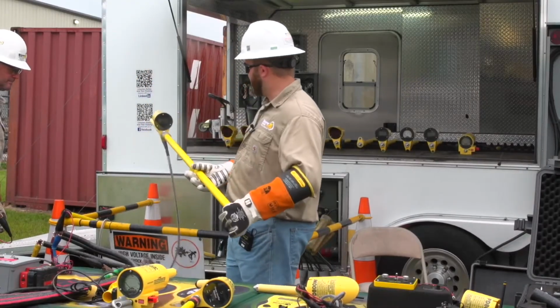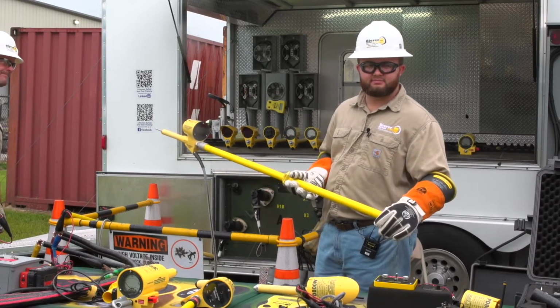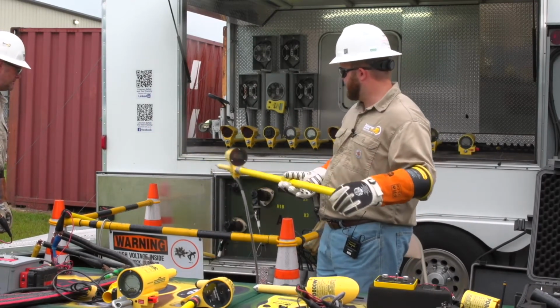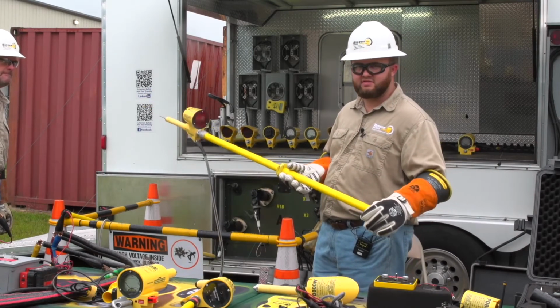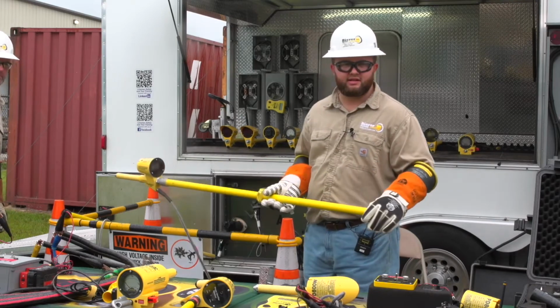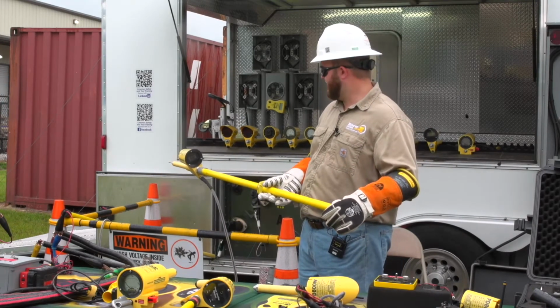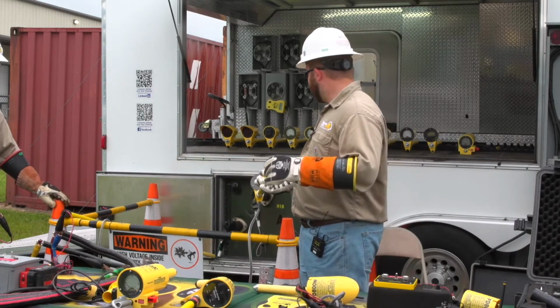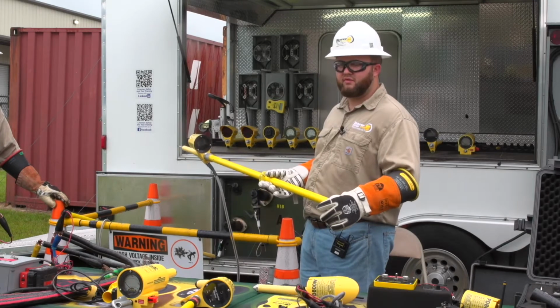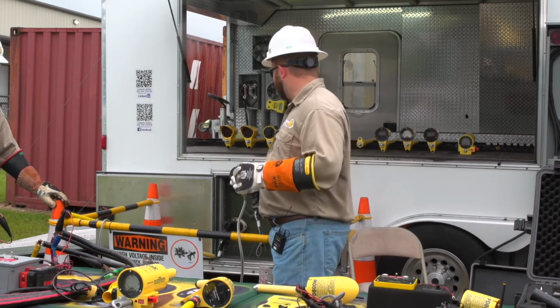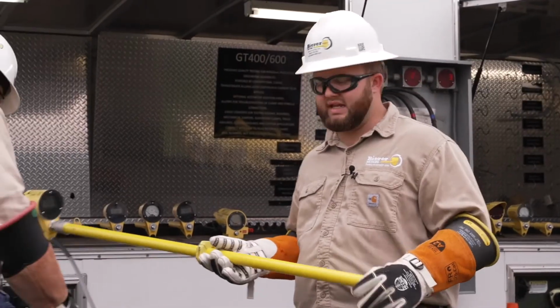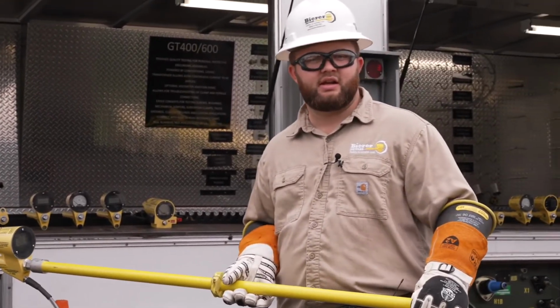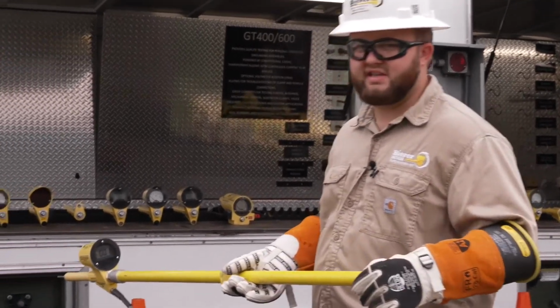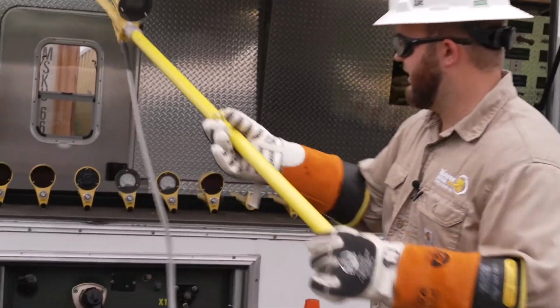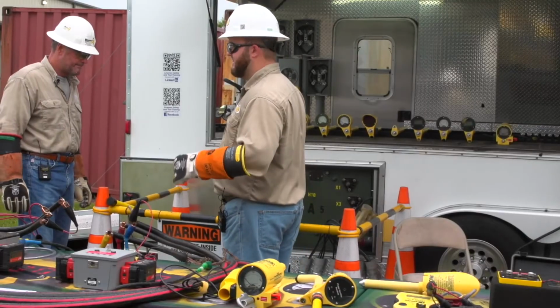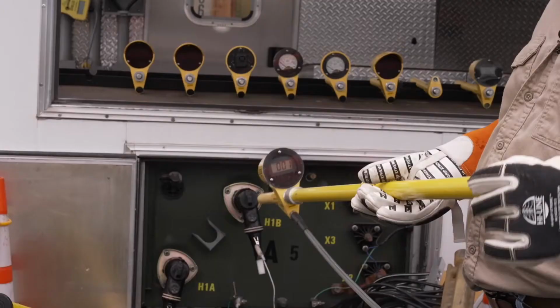So the first thing you're going to want to do using the device, since this is a little bit unusual, using a digital device to phase off capacitive test points, is take a phase to ground reading. The reason is for a couple of reasons. The main reason is that since this tool is going to give you accuracy within 1 volt, you're going to see that those elbows may have cured different, although they're the same age. They may have been made by the same manufacturer. The elbow's cured a little bit different, so that capacitive test point value may be a little bit different at each elbow. So you're going to do a little bit of math, similar to phasing with one of these tools on an overhead conductor primary power.